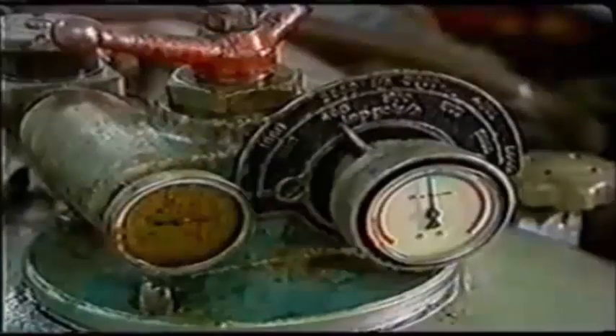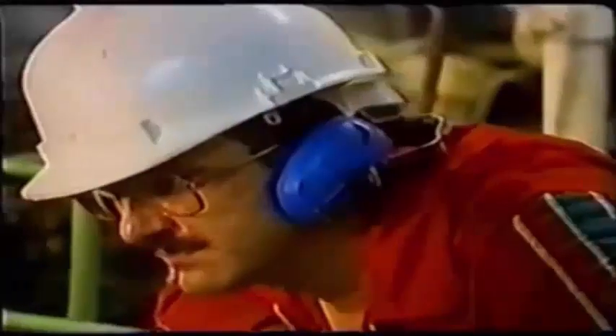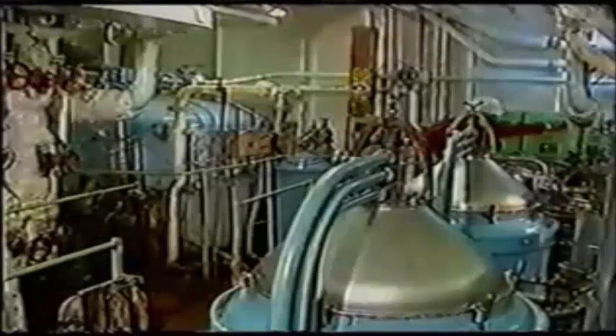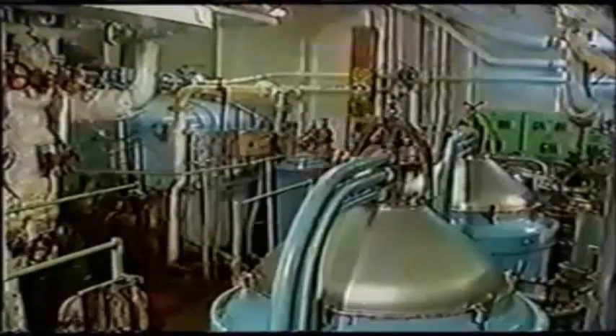The ingress of water into the system is always a danger, and frequent checks should be carried out on the system oil to ensure an early detection and removal of water. This is most important, as the presence of water increases the risk of corrosion as well as microbial contamination of the oil. The water must be kept out or removed totally as quickly as possible from any system oil. Again, systematic centrifugal cleaning will lower these risks.